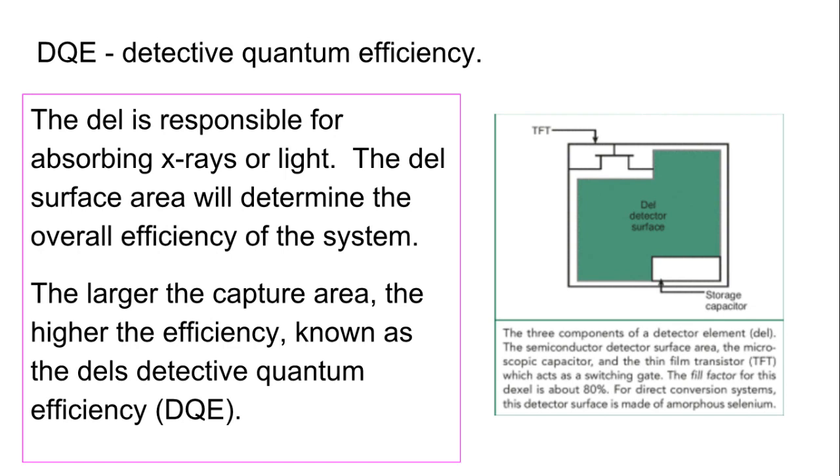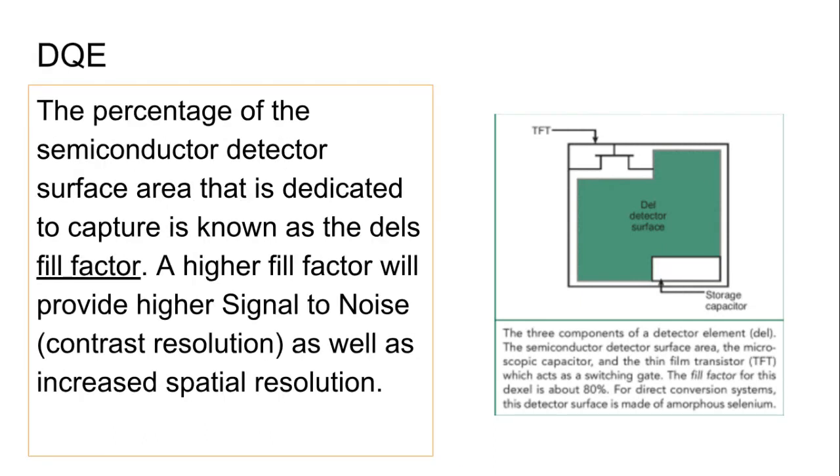Theoretically, if we have an increased fill factor, we could typically lower the dose a bit. The percentage of the semiconductor detector surface area that is dedicated to capture, as we've been saying, is known as the fill factor. Again, a higher fill factor will give you better overall resolution.